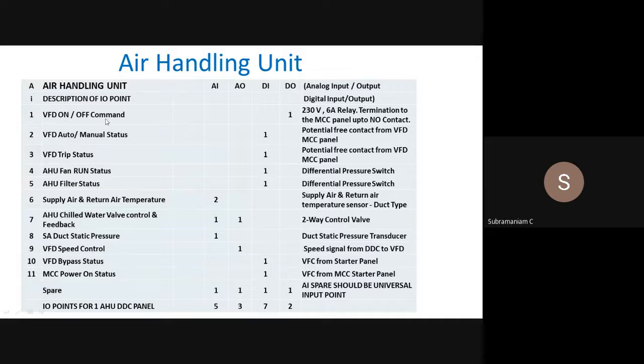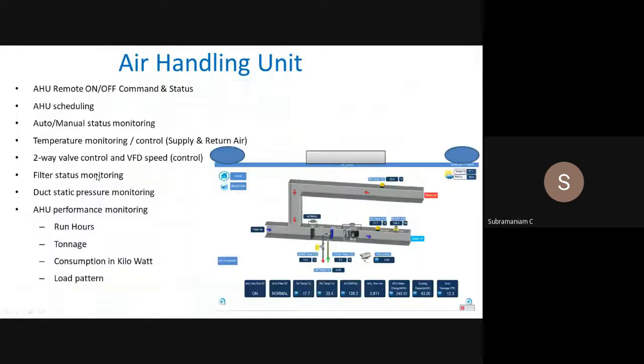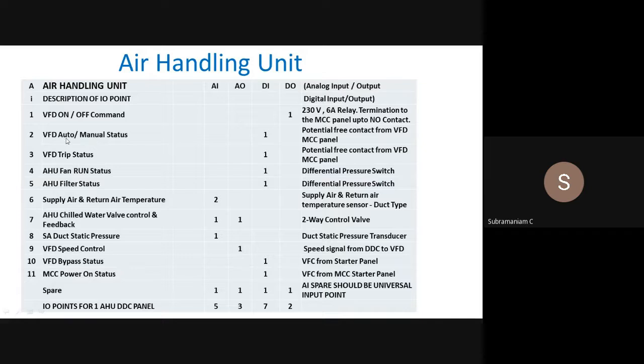If it is a VFD on/off, it is a binary output, because it is a command from the controller to the starter to start the motor. That is an output, which is called a DO. After the AHU is started, you should know whether it is running. You put a differential pressure switch across this fan. That will tell you whether the fan is working or not. But that will happen only if the hand-off-auto switch is in auto mode. For example, if a mechanic has gone there to inspect the AHU, he might have put it in manual mode. Then BMS will not do anything.